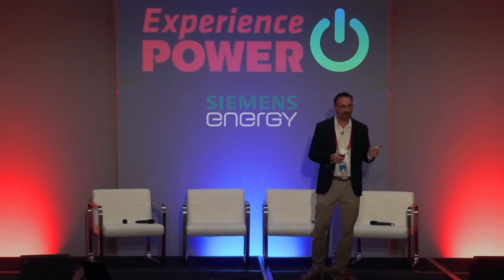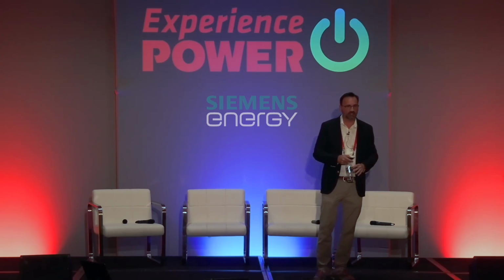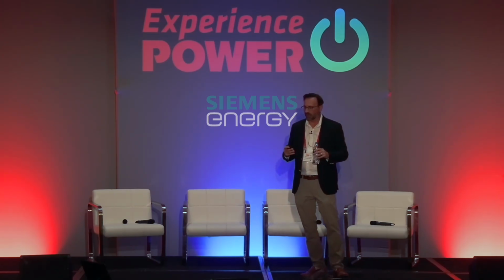I said you need a model of your energy system so that you can run simulations and forecast capacity, right? This is a visual representation of what an energy system model might look like from us. So what we do is we have a library of component models. We want to be able to model every single controllable asset at the power plant. You want to establish connections between these assets because the output from one could be the input for another, right? A simple example would be the heat output from a gas turbine is going to go into your HRSG, right, for creating steam. So there's a relationship between all of these different assets, and you want to establish that connection.